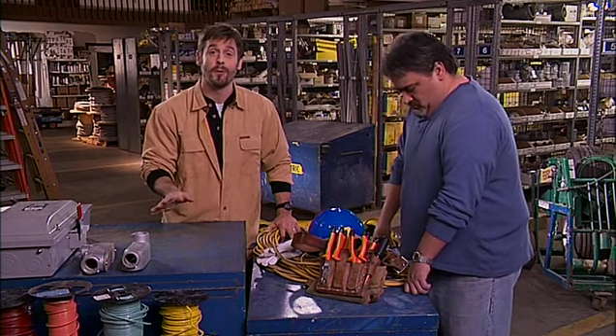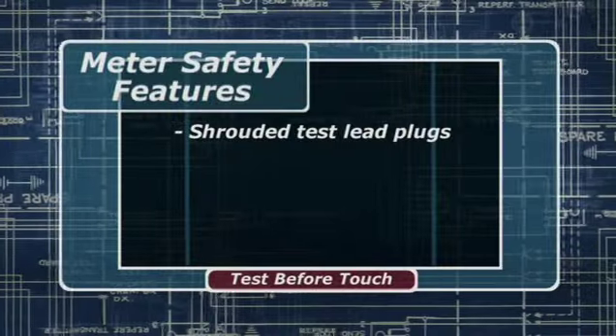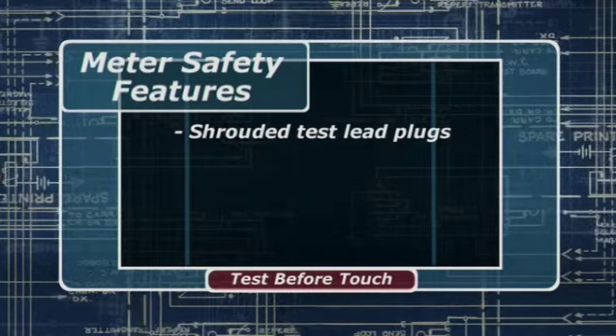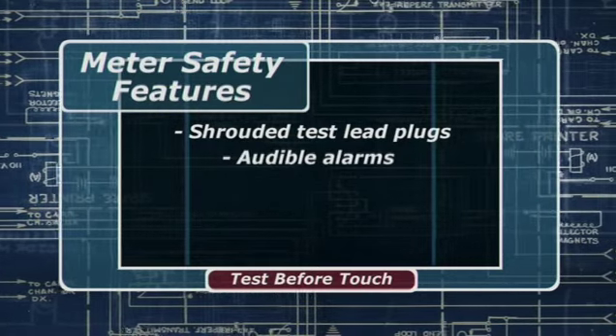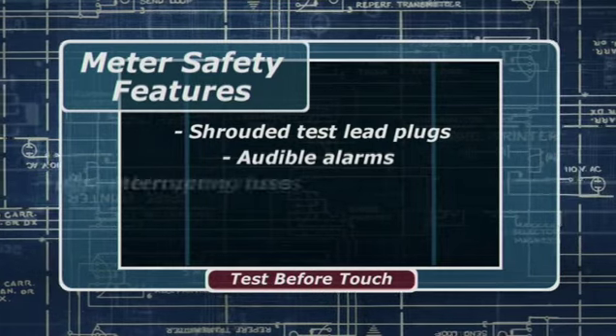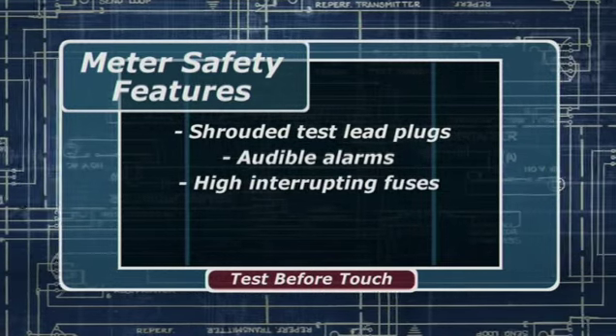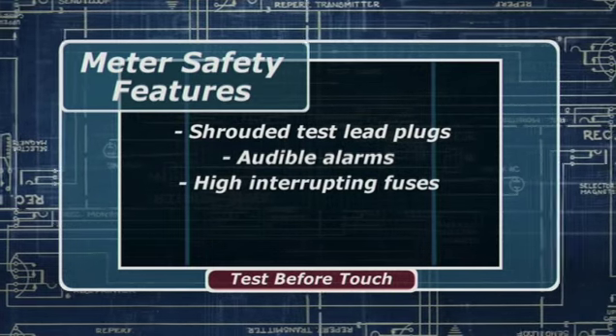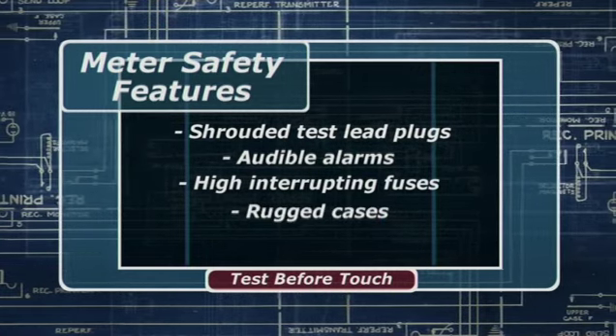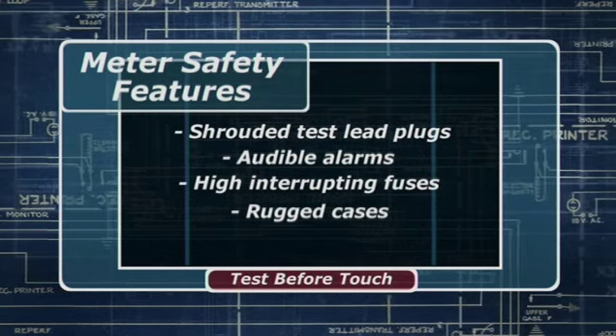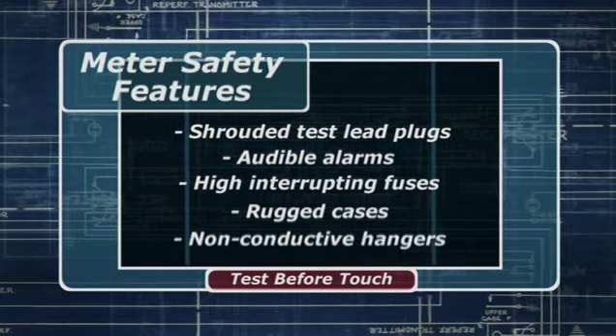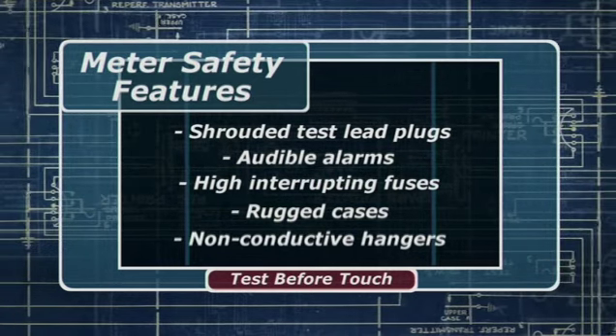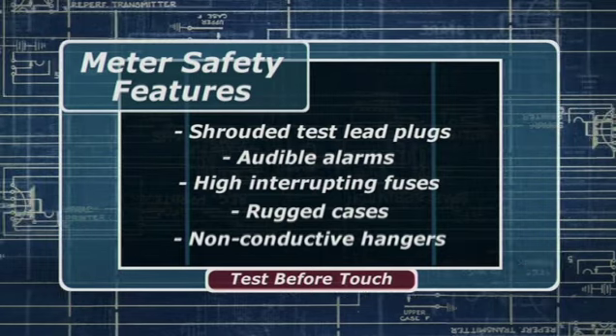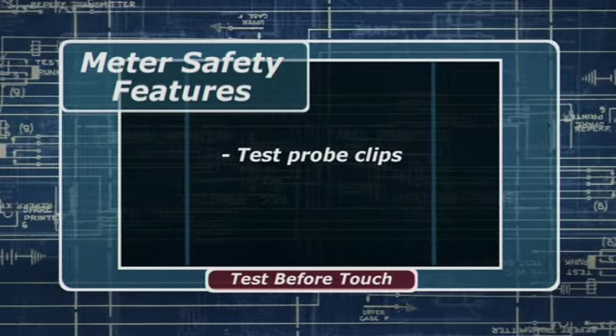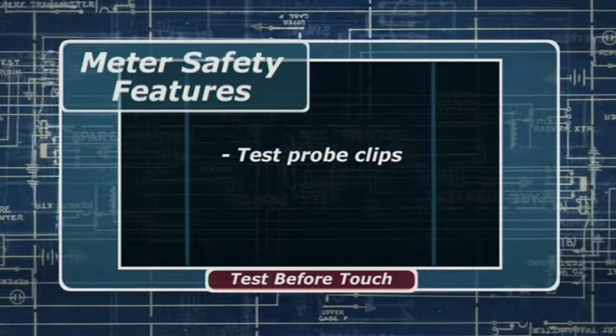Okay, well, whichever meter you order, make sure that it has a number of safety features, like shrouded test lead plugs that limit exposed conductive parts, even when not inserted. Audible alarms that sound when your test lead connections don't agree with the switch setting. High interrupting fuses in current measuring circuits. These help prevent destructive current if the meter isn't connected properly. And look for rugged cases. Most meters get banged around in the field, and you're going to want something that's going to keep working reliably. You want hangers on the meter case. You need both hands to make measurements without having to hold your meter. And the same with the probes. You want test probe clips to make it easier to access the test point safely.